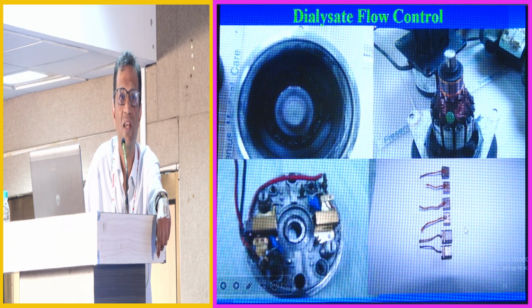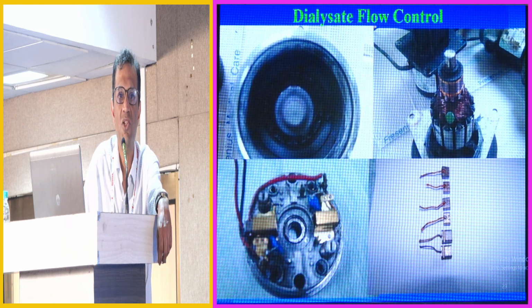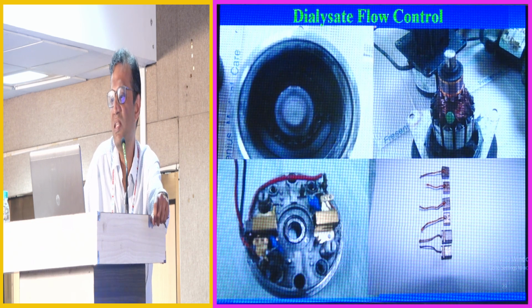So after about 18,000 hours, for the degassing motor's pump, either the brushes will have to be changed or the motor itself will have to be changed, and after 22,000 hours, the flow pump will usually meet with the same fate.